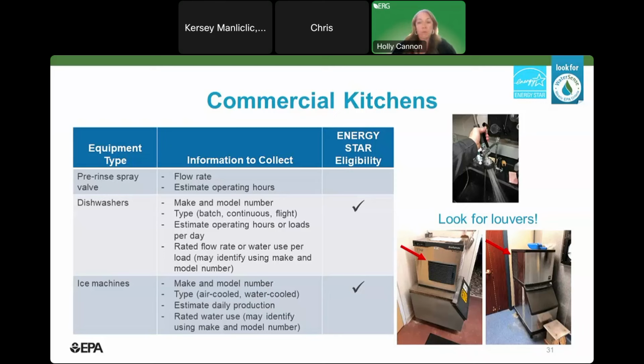The water use you can maybe look up later using that make and model number. For ice machines, the primary thing you're going to want to note is whether it's water-cooled or air-cooled. Water-cooled models often use single-pass cooling water, and air-cooled models are much more water efficient. You can easily identify air-cooled models by looking for louvers on the side of the ice machine, and if you're not sure, you can look up the model number. Oftentimes, the end of the model number has a W or an A at the end that can tell you water-cooled or air-cooled. You could also check the floor drain to see if cooling water is flowing.